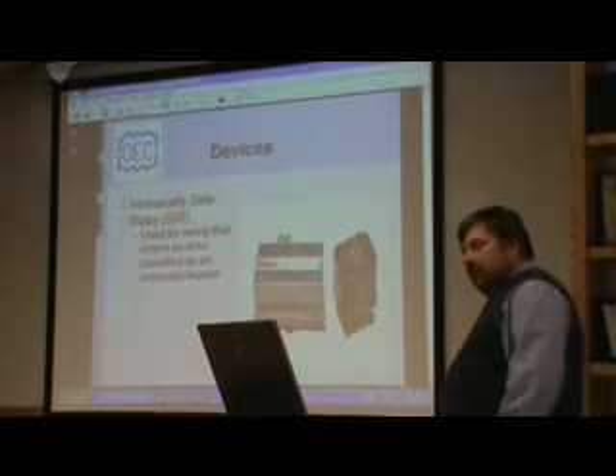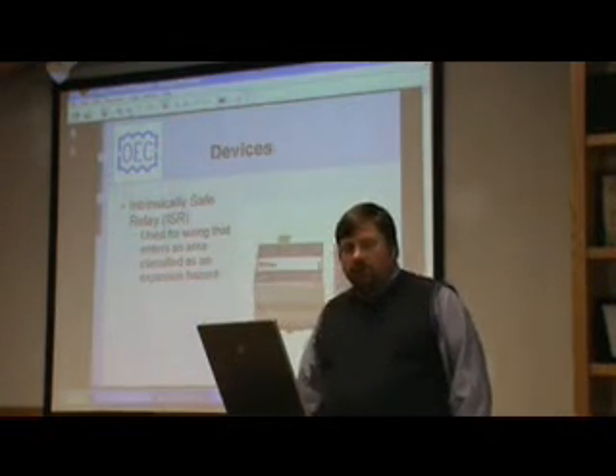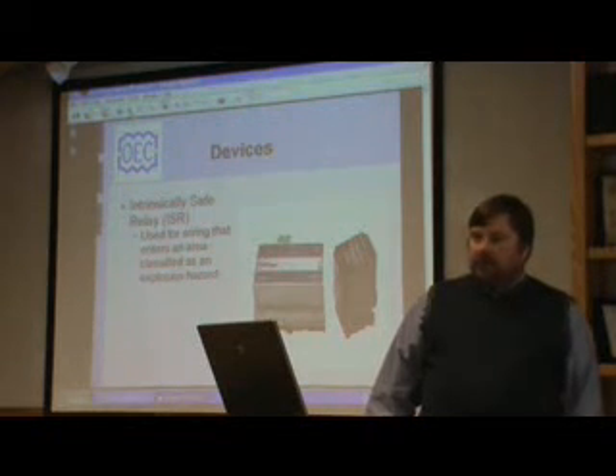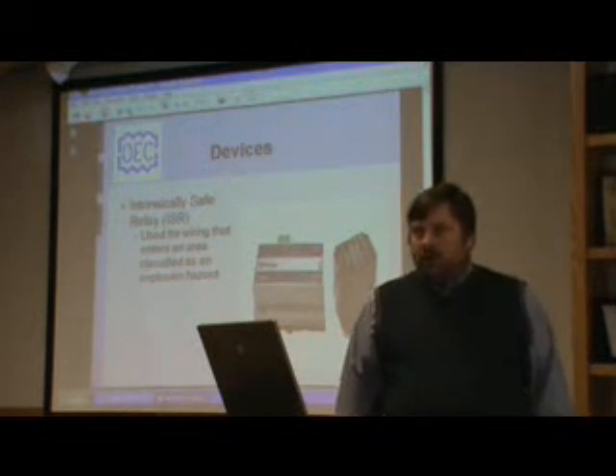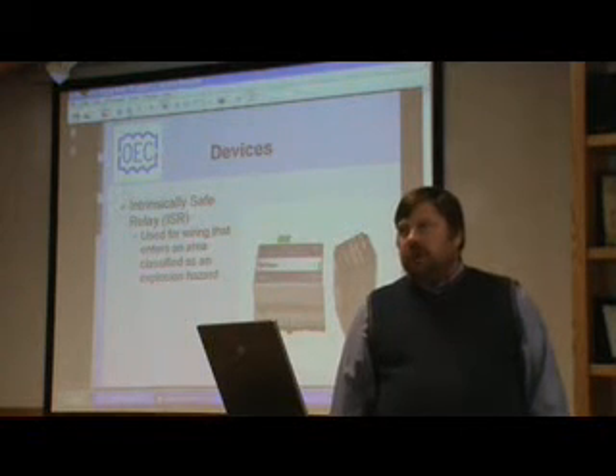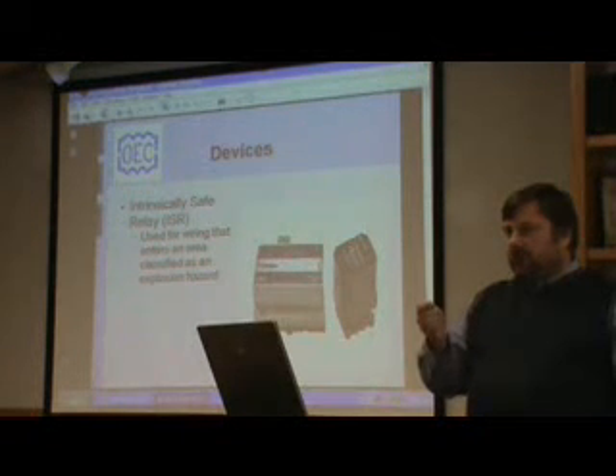As we get more and more into classifications for wet wells, I'm seeing that they're calling out more for intrinsically safe relays. And what the intrinsically safe relay does in your panel is any wire that goes into, like the wet well is classified as a gas environment, it causes a non-sparking environment so that if something happens to the wire on the float switch, you're not going to cause a spark and make the wet well explode.